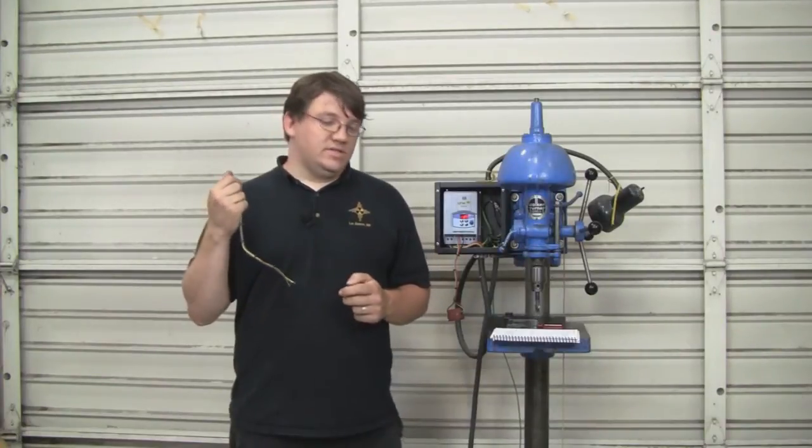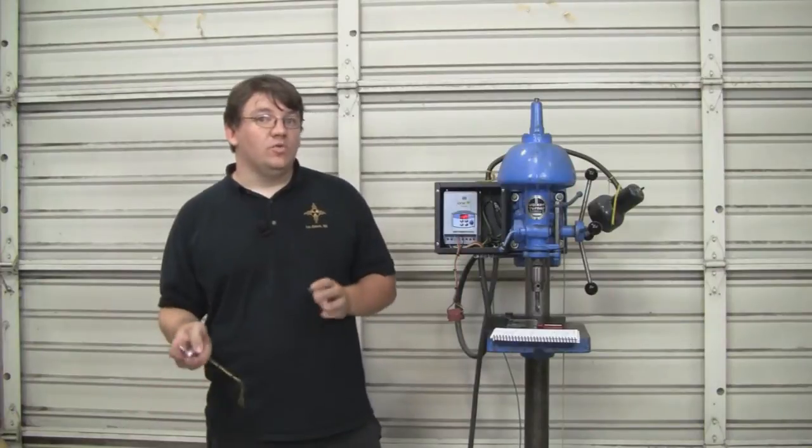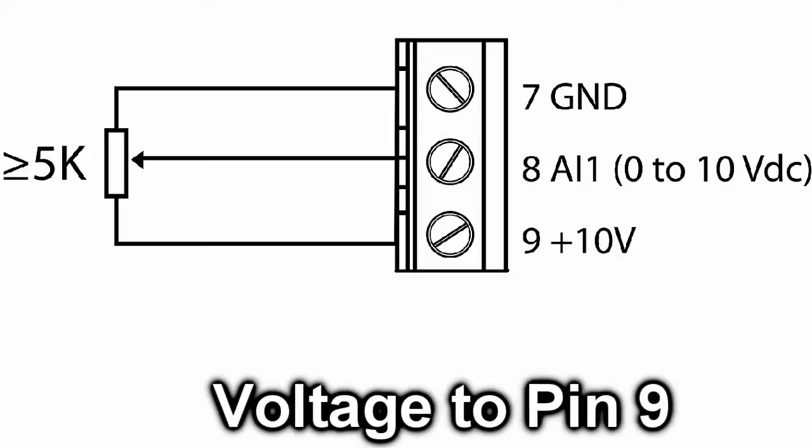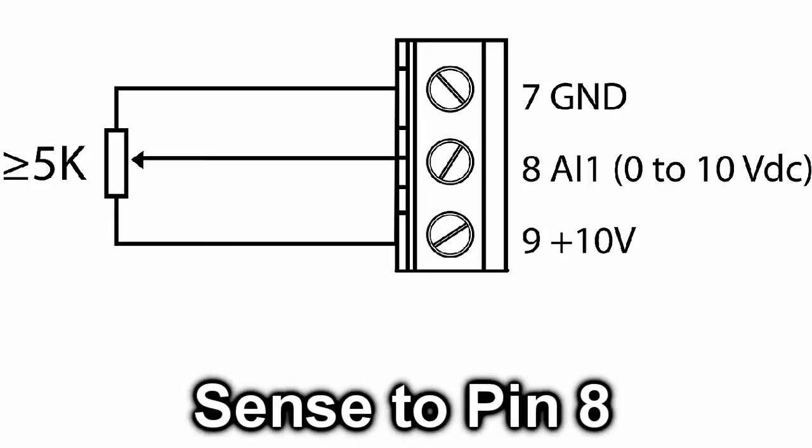Now, on the CFW10, ground is going to be hooked to pin 7, voltage will be hooked up to pin 9, and then sense, which is the varying resistance across the two, is going to be on pin 8.